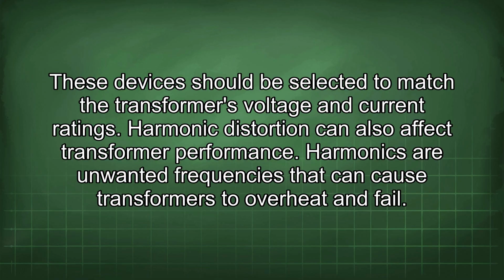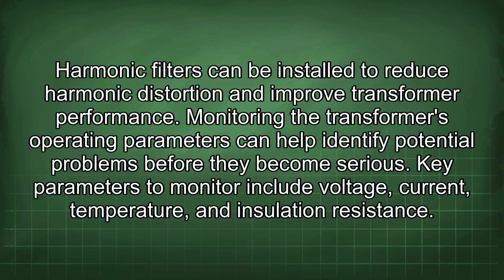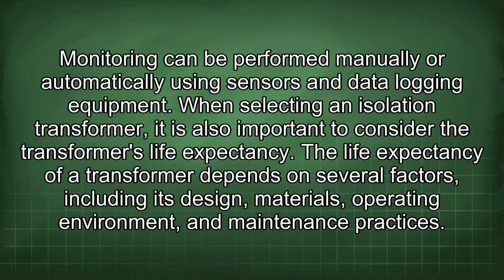Harmonic distortion can also affect transformer performance. Harmonics are unwanted frequencies that can cause transformers to overheat and fail. Harmonic filters can be installed to reduce harmonic distortion and improve transformer performance. Monitoring the transformer's operating parameters can help identify potential problems before they become serious. Key parameters to monitor include voltage, current, temperature, and insulation resistance. Monitoring can be performed manually or automatically using sensors and data logging equipment.